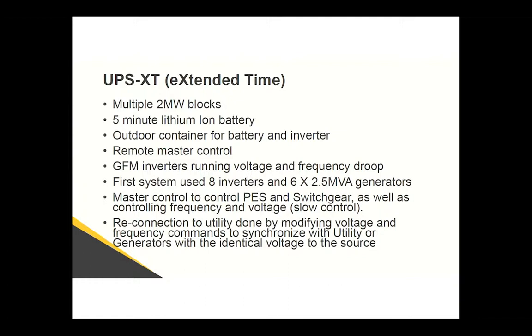Still an offline UPS. Now we have a remote master control, so we don't care what inverters are online or offline. And we have grid forming inverters that are running both voltage and frequency droop, where the need for communication is really a slow need rather than a fast need. So they just adjust to the new voltage and VARs very quickly. Our first system used 8 inverters, 6 of them 1 megawatt, 1.25 MVA inverters, with 6 2.5 MVA generators.